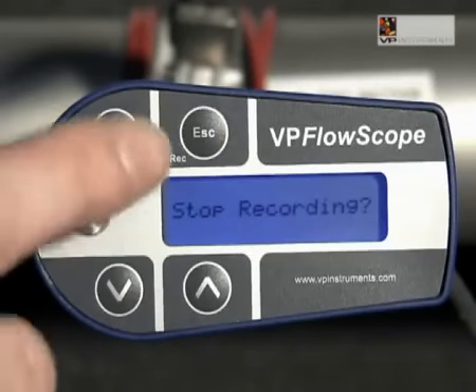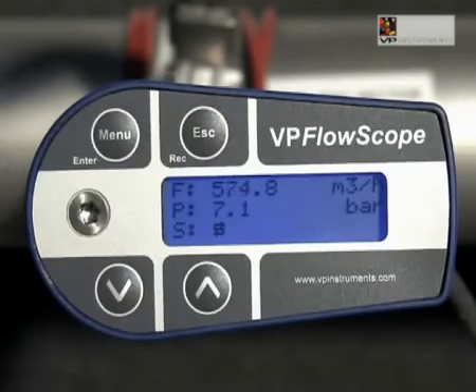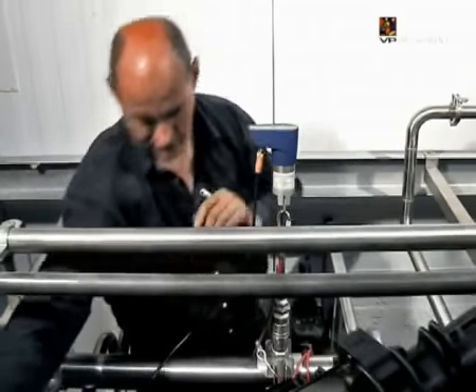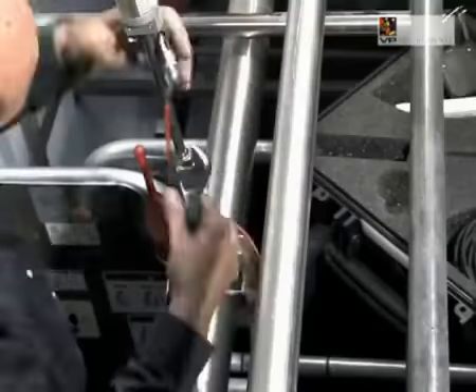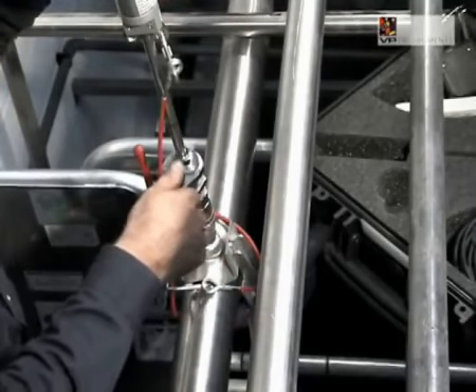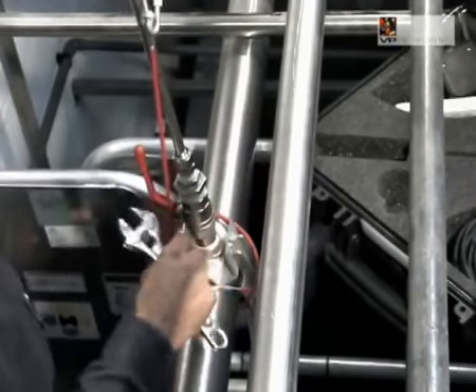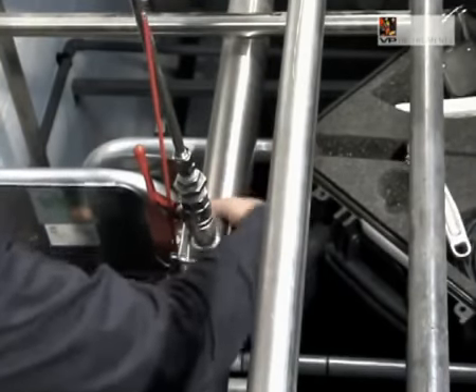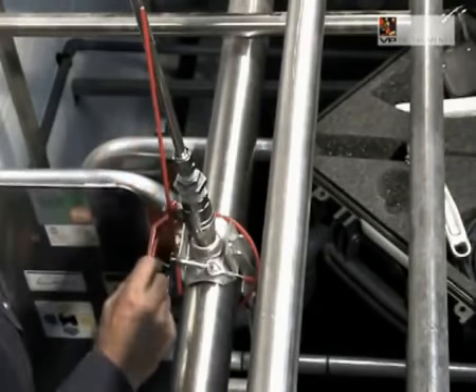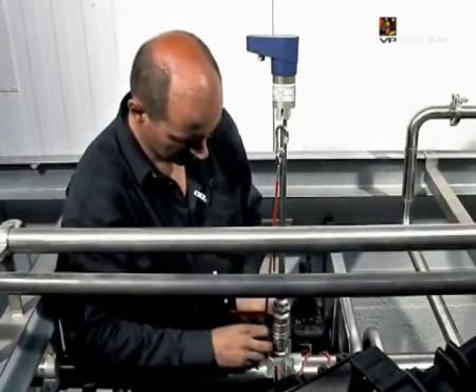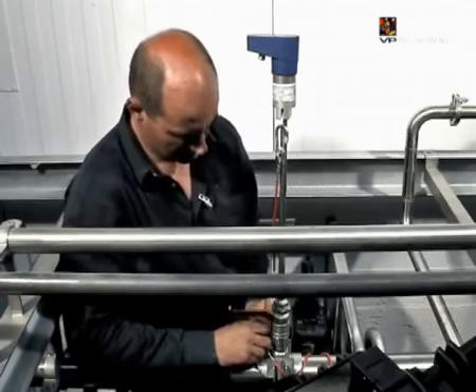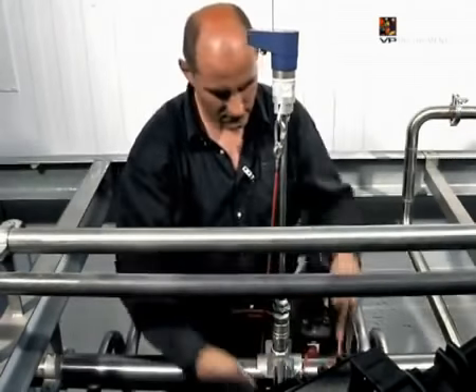When your measurement is finished, you can retrieve the data from the VPFlowScope. You can hook up the VPFlowScope to your computer on site and read out the data logger. However, we choose to remove the VPFlowScope and read it out at the office. First, stop recording. To stop recording, press Escape and then Enter to confirm. Disconnect the VPFlowScope.